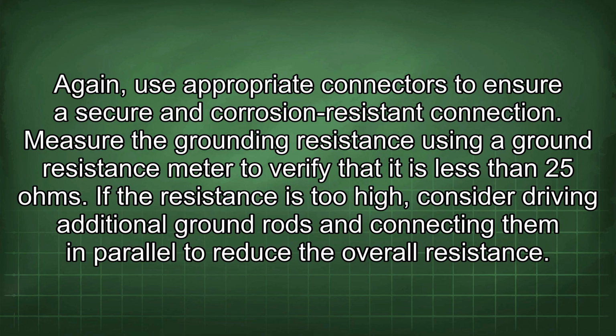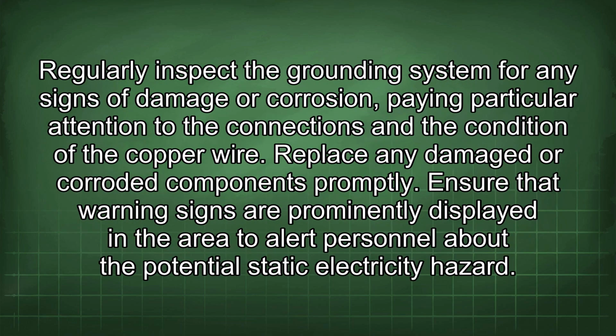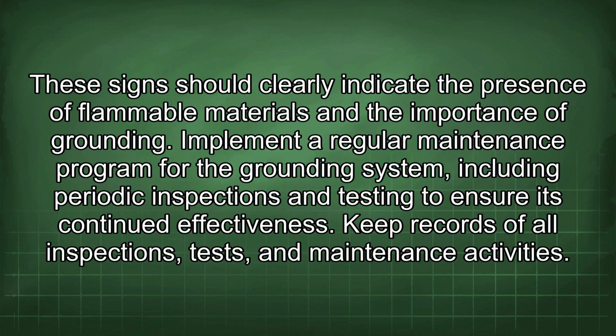If the resistance is too high, consider driving additional ground rods and connecting them in parallel to reduce the overall resistance. Regularly inspect the grounding system for any signs of damage or corrosion, paying particular attention to the connections and the condition of the copper wire. Replace any damaged or corroded components promptly. Ensure that warning signs are prominently displayed in the area to alert personnel about the potential static electricity hazard. These signs should clearly indicate the presence of flammable materials and the importance of grounding.